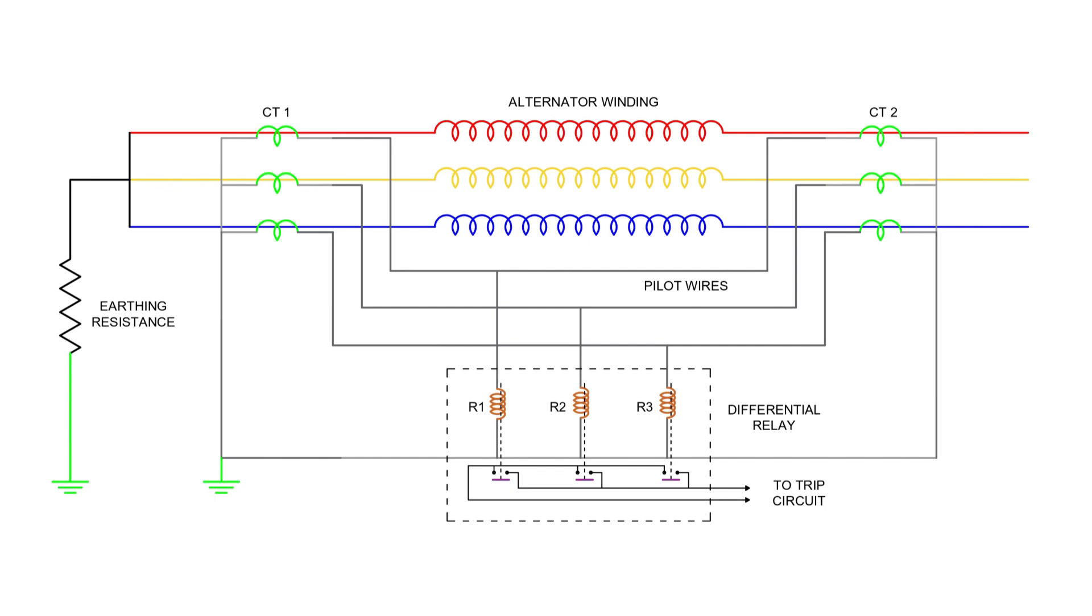The relay coils, one for each phase, are also connected in a star configuration, with the neutral point tied to the CT common point. Each outer end of the relay coils connects to its respective pilot wire. The pilot wires are connected between equipotential points in the system, ensuring equal voltage and no current flow through the relays under healthy conditions.